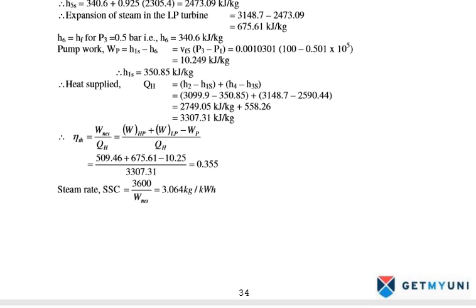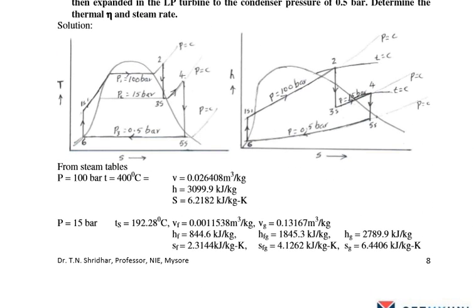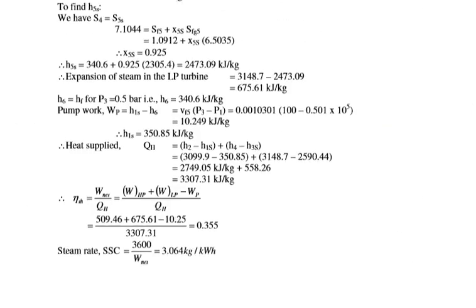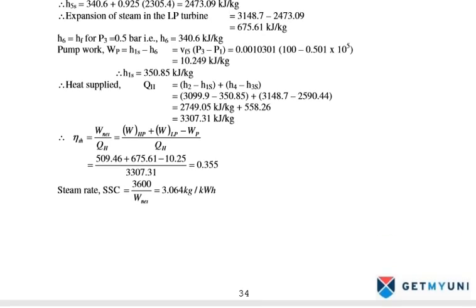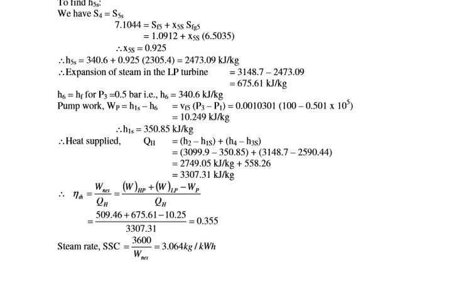Now find the heat supplied. Heat addition takes place from H1 to H2 in the boiler, and from H3 to H4 in the reheater. Applying the equation: QH = (H2 minus H1S) + (H4 minus H3S) = 3099.9 minus 350.85 plus 3148.7 minus 2590.44 = 3307.31 kJ per kg.